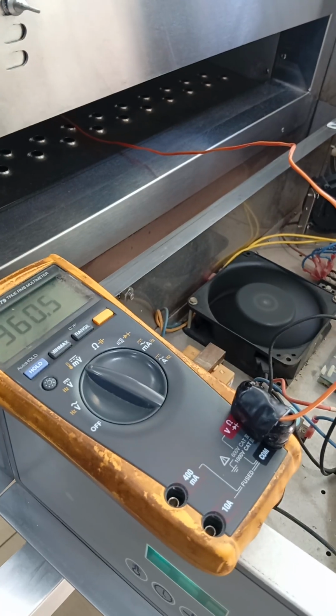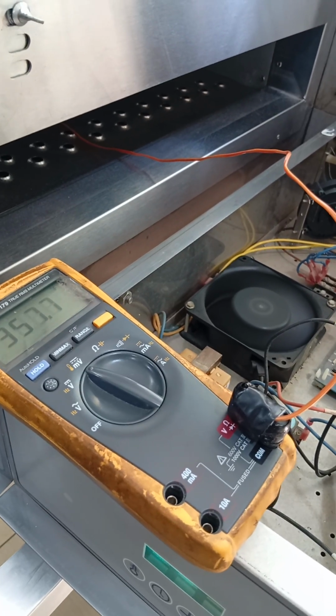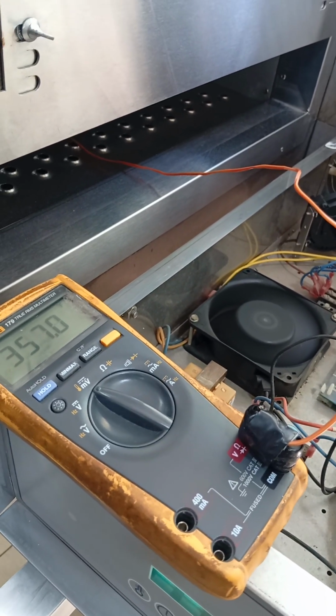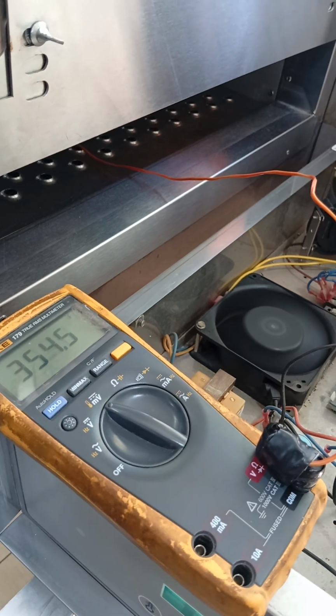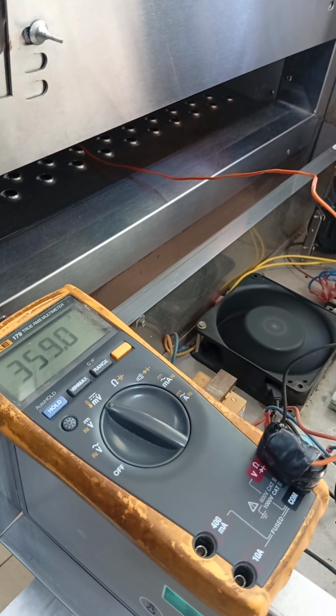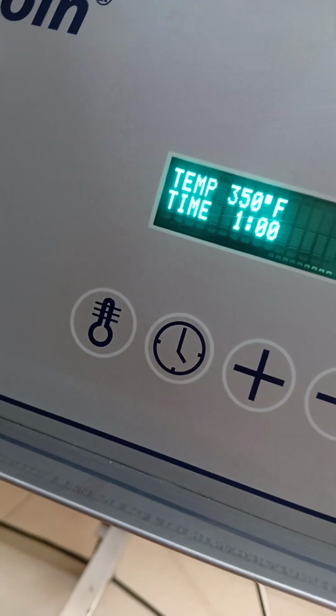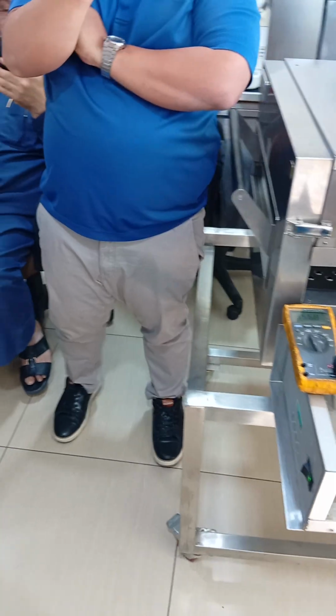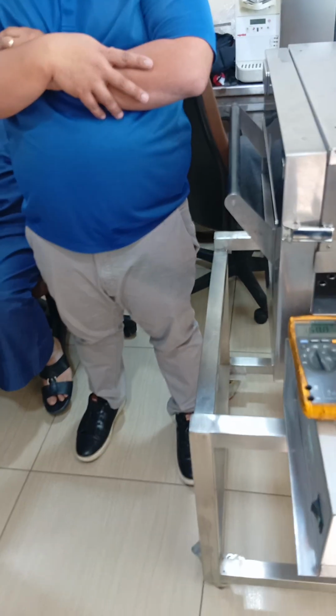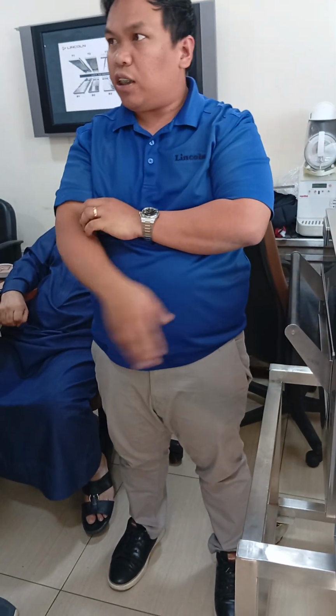360 maximum. Okay. 357 and then 54. Okay, 55 plus or minus 10. It's okay. If you want, try someone just to adjust the addition. Just add minus, because it's still a 10 degree difference from the set point. Now you can adjust. At least you will practice how to enter.